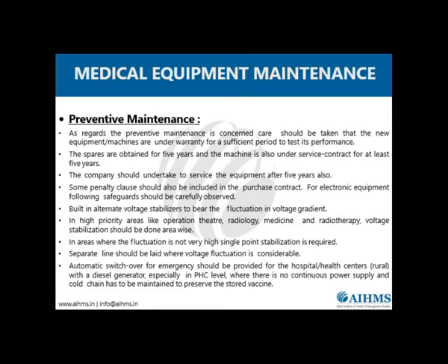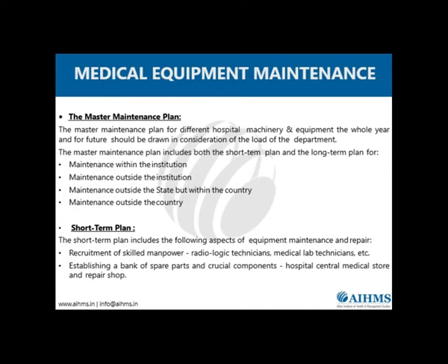Similarly, a provision for automatic switchover for emergencies should be provided, because there has to be an uninterrupted power supply in these areas, since these are critical areas for the sustenance of the patient. Then you have to prepare a master maintenance plan, which is within the institution, outside the institution, outside the state but within the country, and outside the country.